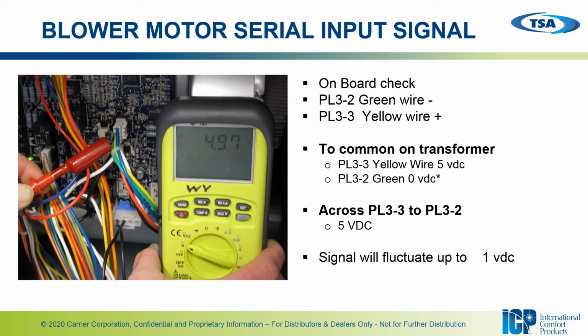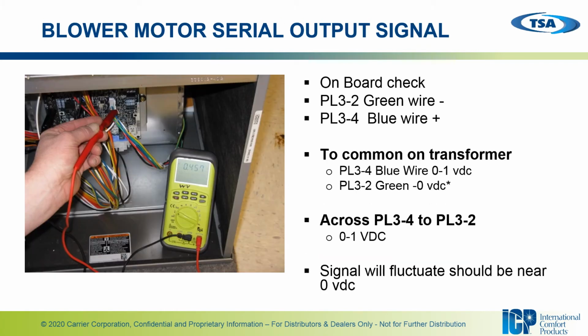Now, if you're wanting to check what we call the serial input signal or the speed control signal, you're going to check that between 3-2 and 3-3, which is the yellow wire and the green wire. The green wire is essentially the common back to the transformer or ground, and your yellow wire should be a 0 to 5 volt DC signal, which is your speed signal to the motor. Okay, so you should be reading 5 volts DC across plug 3-3 and plug 3-2, which is your yellow and green wire. The signal will fluctuate up to 1 volt. And you can also check at the other end on the control board to verify that the signal is coming from the control board.